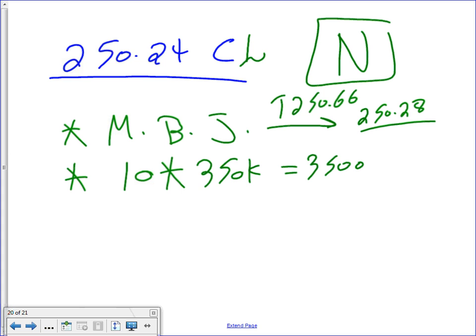That will get you 3500 kcm, right? Why did I multiply? This is the size in kcm. This is the size of the conductor, the service conductor. Where does the 10 come from? Because each one of these conductors actually has 10 in it.